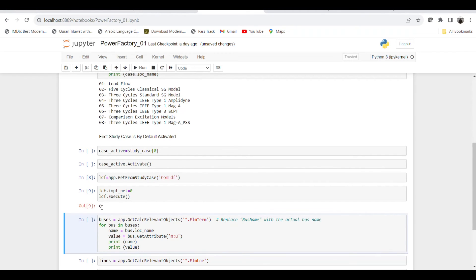We get a return value of zero, meaning the load flow case has been run successfully. Now that the load flow has been run, we can extract results from this PowerFactory case. First, we will learn how to retrieve bus voltages. We use 'GetCalcRelevantObjects' and within those relevant objects we are interested in all elements related to 'ElmTerm', which represents terminal elements — essentially the buses in the system.